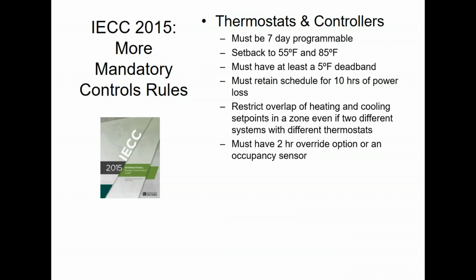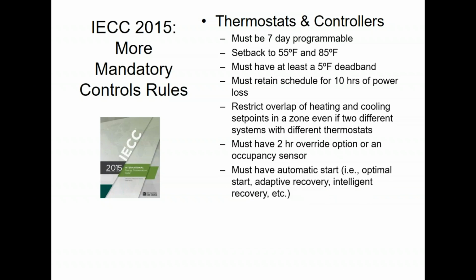That is not permitted. You got to have some way for the occupants to override the thermostat in a normal fashion, as opposed to using paper clips and jamming them into the lockbox. They got to have some kind of normal method, either with an occupancy sensor or an override button. You have to have an adaptive intelligent recovery type routine or optimal start, whatever you want to call it. That's where the stat system starts enabling heating and cooling function prior to the occupied time, so the system ends up at the occupied set points at the same time the schedule was supposed to begin.